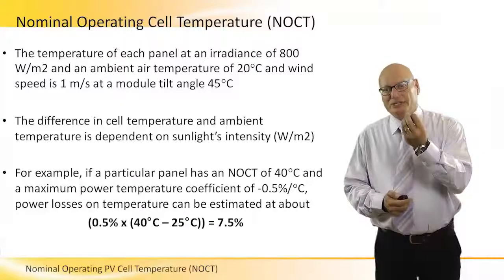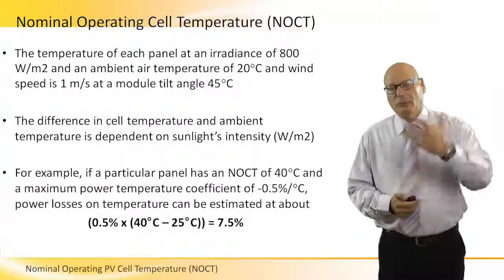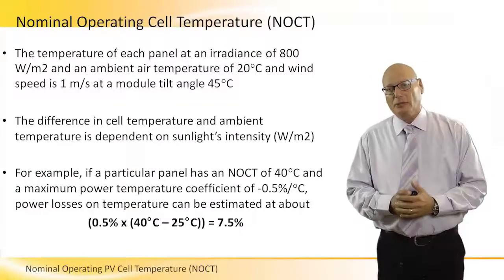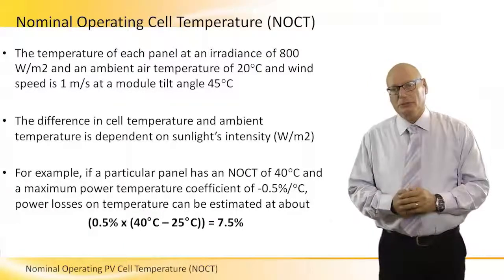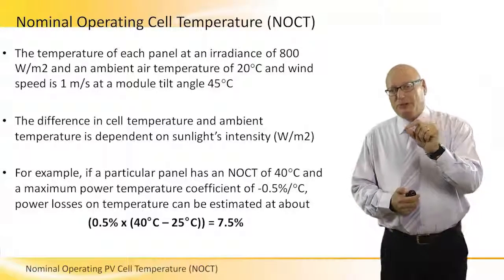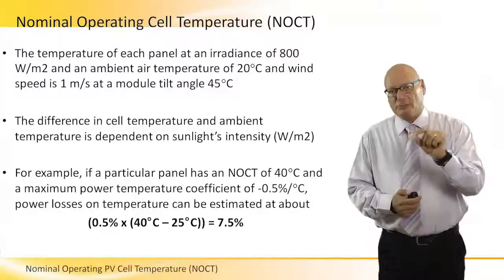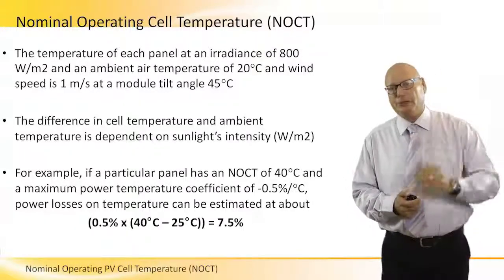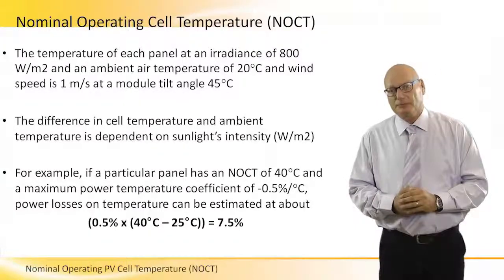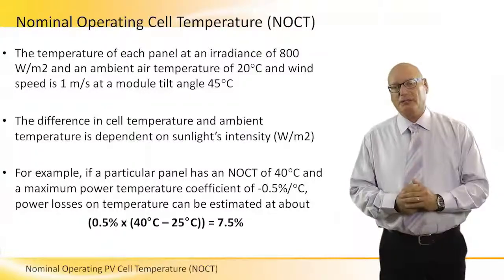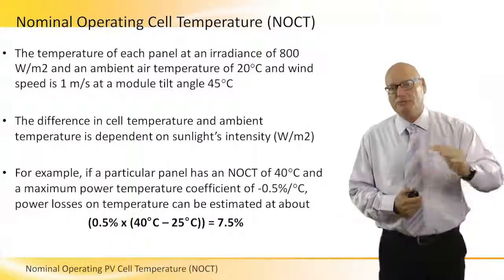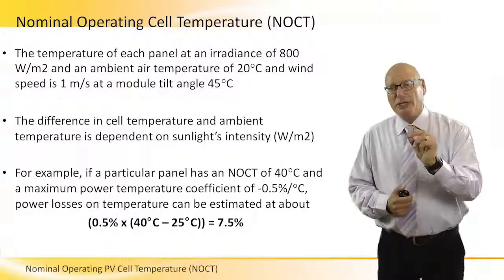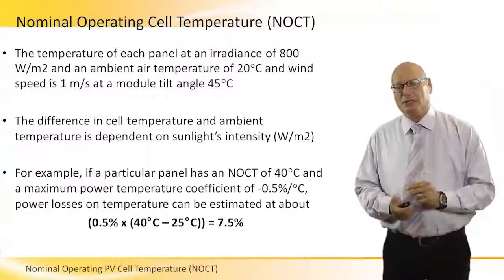So when we select a panel and look at its technical specification, we want to look at the NOCT. First, we want as small a number as possible. 0.5% per degree C above 25°C is a very big number. 0.4% is better, and 0.3% is even better. We have to be careful because the loss is significant.